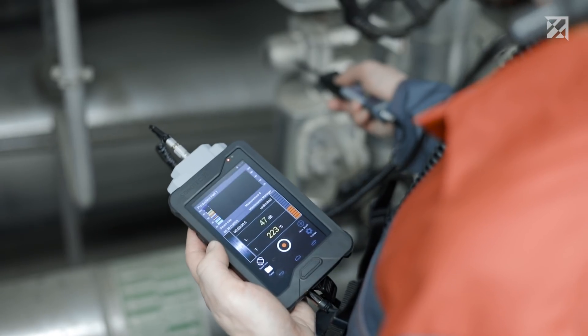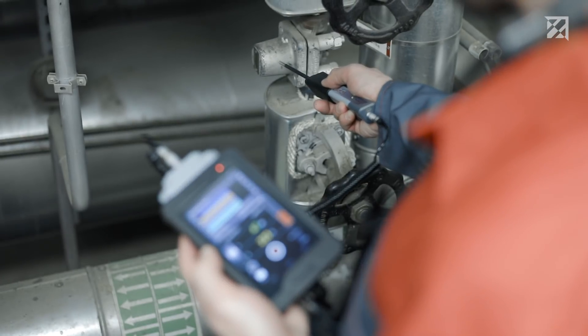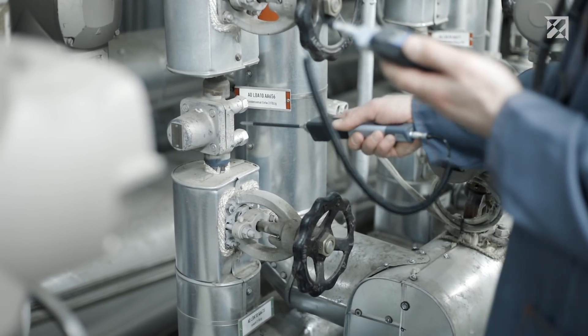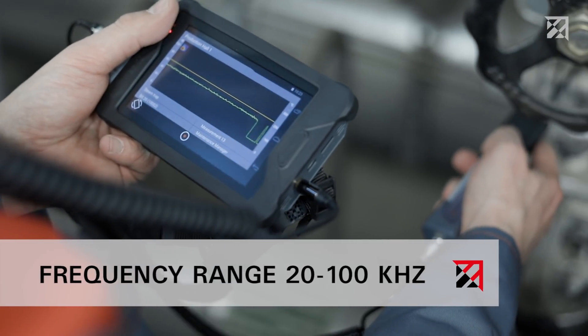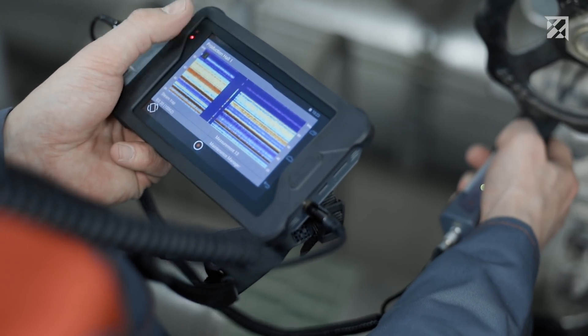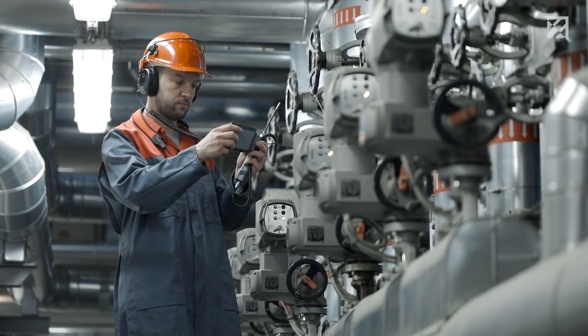In order to ensure a reliable status assessment, a combined measurement of temperature and ultrasound is required. The first step involves measuring the temperature of the steam trap at the inlet and outlet. The ultrasound signal in the frequency range of 20 to 100 kHz is then recorded using the SONAPHONE. Looking at the touch screen and the spectrogram reveals whether the steam trap is working correctly or whether it is defective.